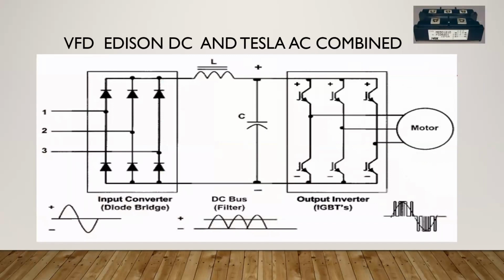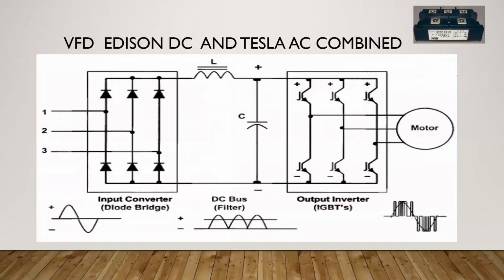And then you have what I call more the VFD design, or electronic, in the marketplace out there that allow you to build through three phase to the motor. And back to the efficiency point, amps times volts basically create power. The three-phase motor being more efficient than single phase, you can pick up 15 to 20% more efficiency by using three-phase motors and putting inverter technology on the front of them instead of doing the other.